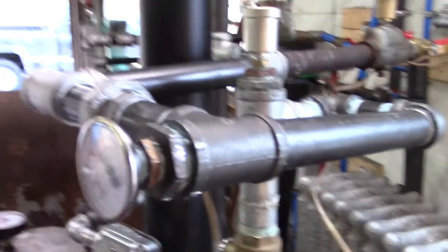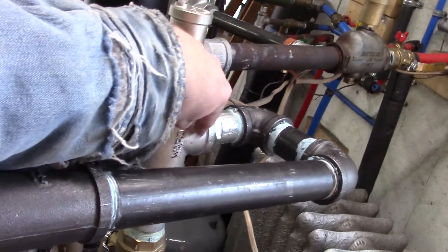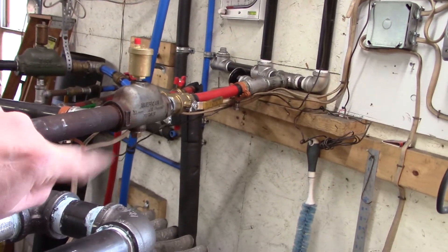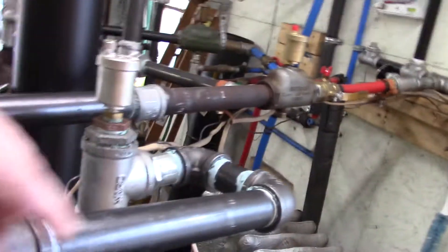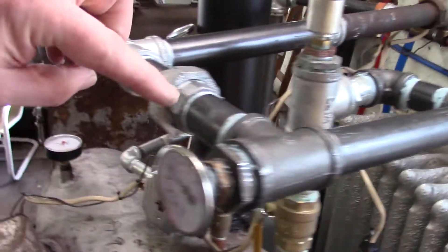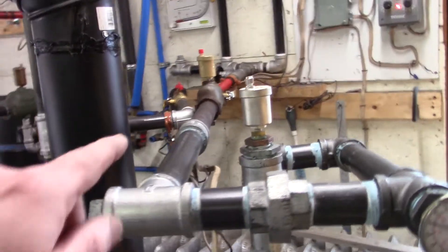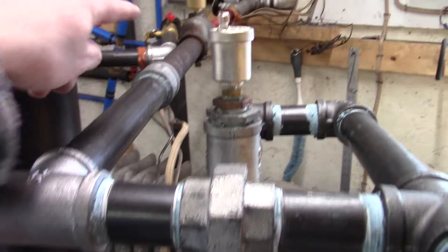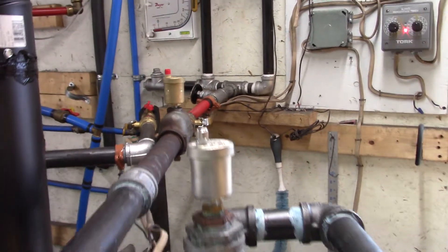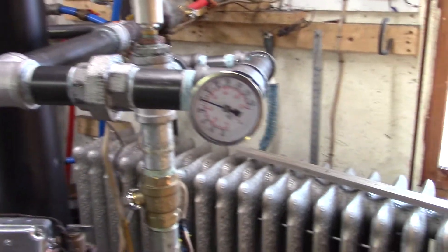Before, it was a piece of one-inch pipe that went from the T off the header straight over to that T over there, and that piece of red pipe too. But now I came up with a complicated trombone here that goes around, and we got about two feet before we get to an air scoop with an air vent in it.